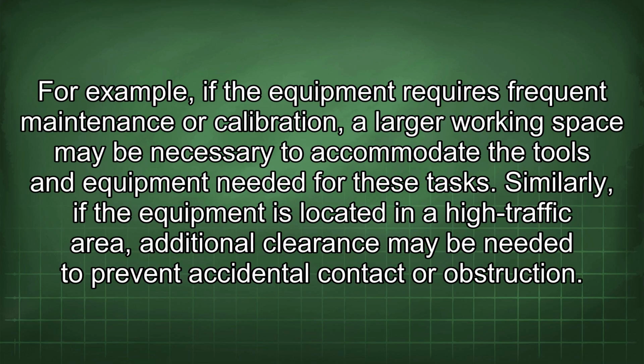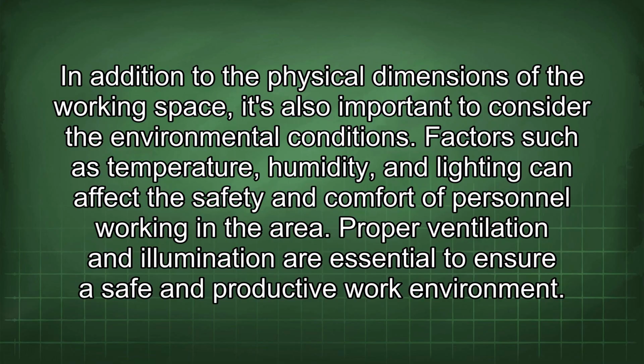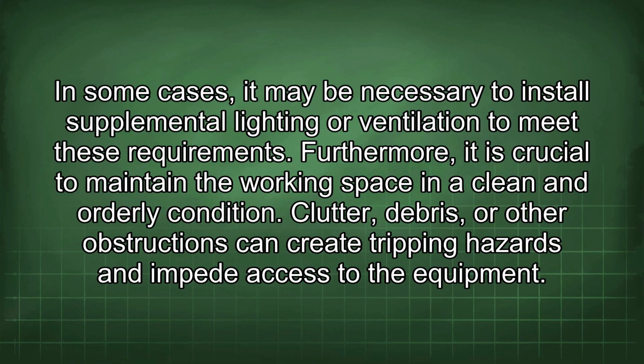For example, if the equipment requires frequent maintenance or calibration, a larger working space may be necessary to accommodate the tools and equipment needed for these tasks. Similarly, if the equipment is located in a high-traffic area, additional clearance may be needed to prevent accidental contact or obstruction. In addition to the physical dimensions of the working space, it's also important to consider the environmental conditions. Factors such as temperature, humidity, and lighting can affect the safety and comfort of personnel working in the area. Proper ventilation and illumination are essential to ensure a safe and productive work environment. In some cases, it may be necessary to install supplemental lighting or ventilation to meet these requirements.